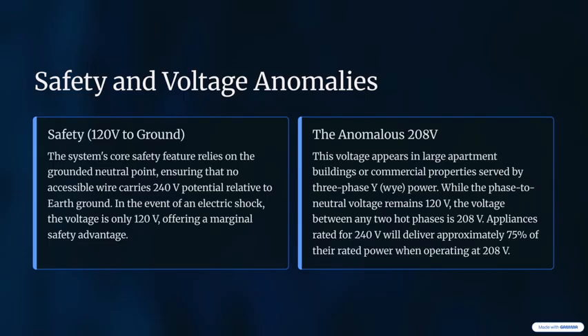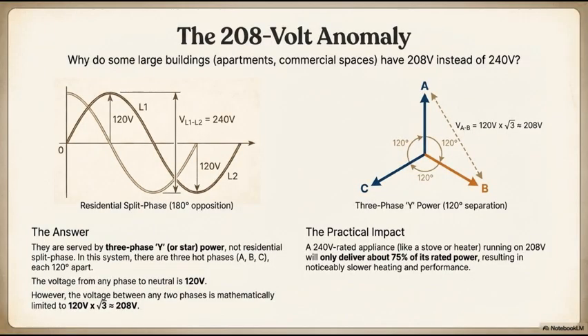You are highlighting an engineering reality of three-phase power, not a systemic failure of the residential split-phase standard. The three-phase system is designed for rotational motor power in industrial settings. The 208-volt measurement is the unavoidable consequence of the geometry of the Y-connected system when you demand a 120-volt link to neutral. It's a purposeful engineering trade-off. It prioritizes providing a balanced three-phase supply while also maintaining that crucial 120-volt safety link. You're not forced into compromise, you're making a choice to use the most versatile configuration.